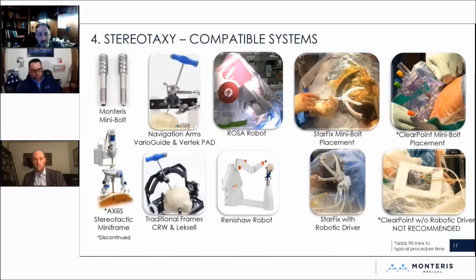In my workflow, you typically get 1 pass at this. So the Monteris bolt makes this very easy. You do your stereotaxis, you put the bolt in, and that stereotactic trajectory is fixed, whether you're putting the laser in right then or downstairs. But you can't easily change it, particularly if you're downstairs in MRI. If you're off, you won't have another opportunity to readjust, to make a small deviation and get it right the second time. So for that reason, we've gone to the Starfix frame, which we know to be very accurate and reliable.